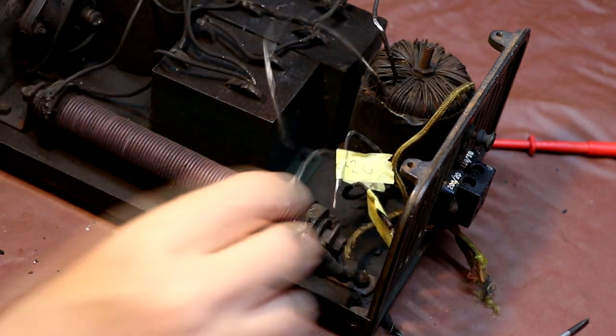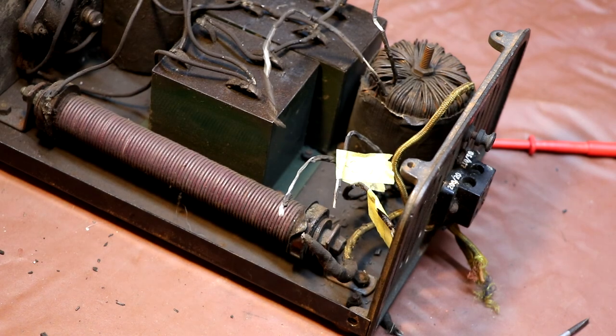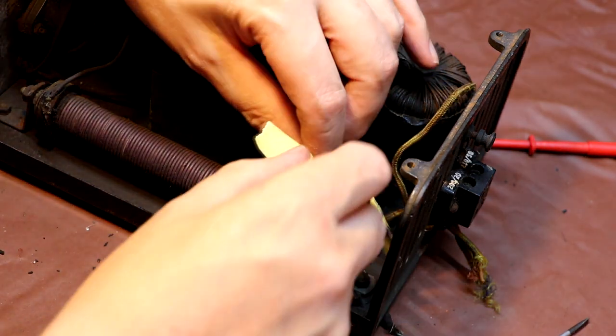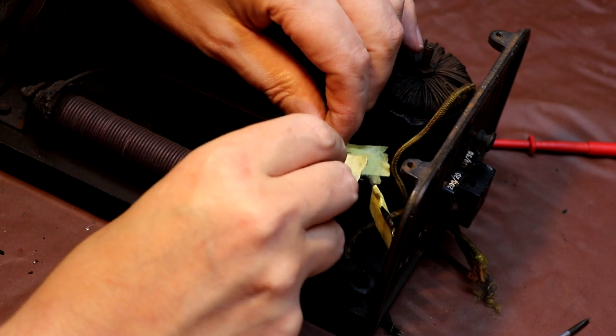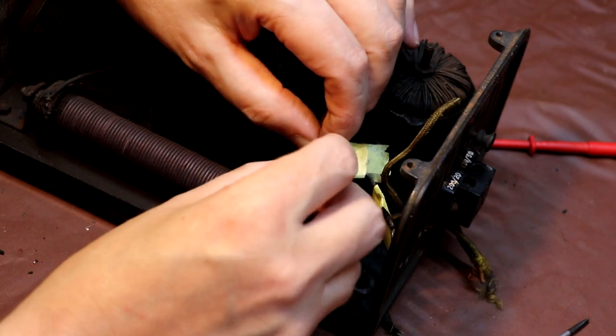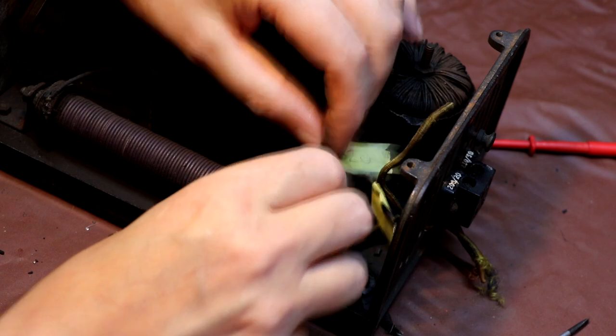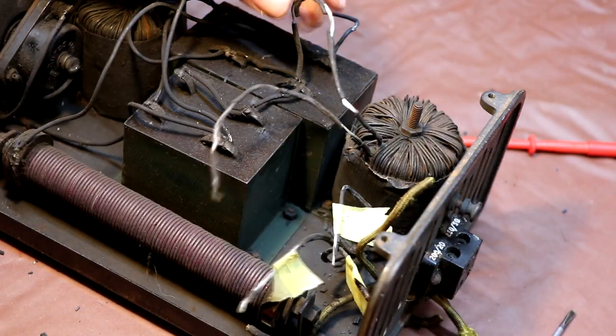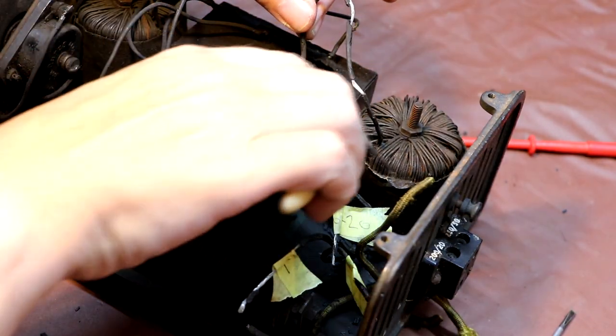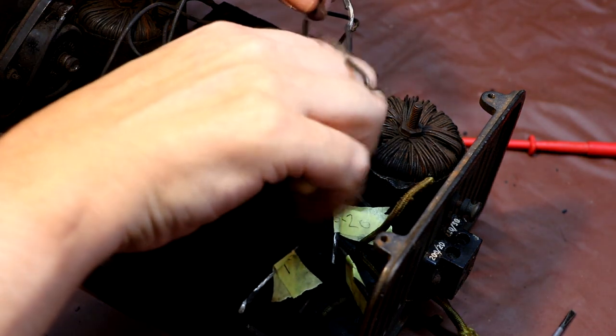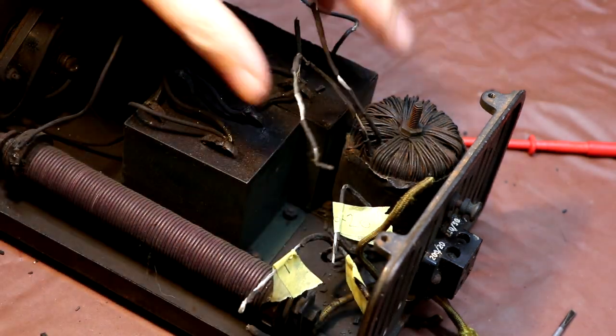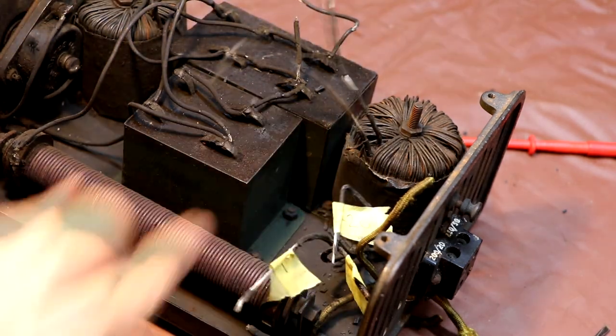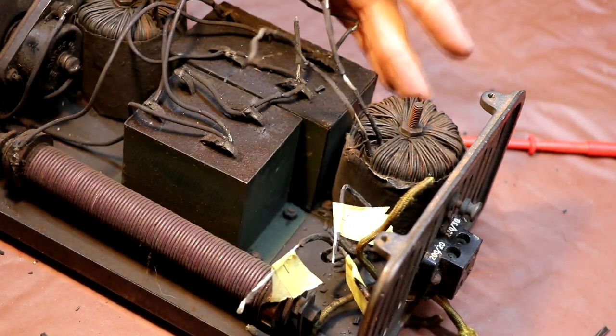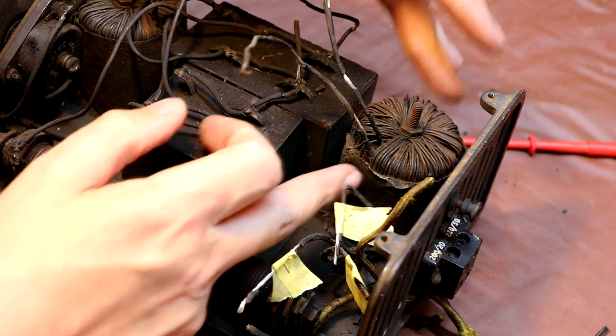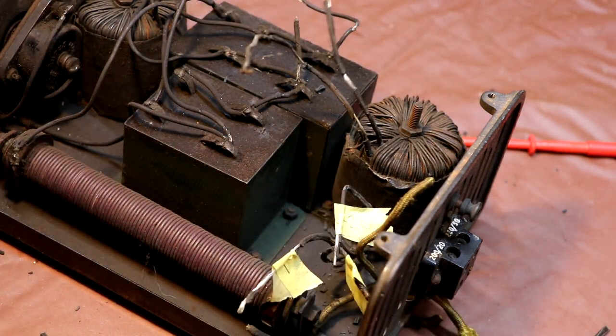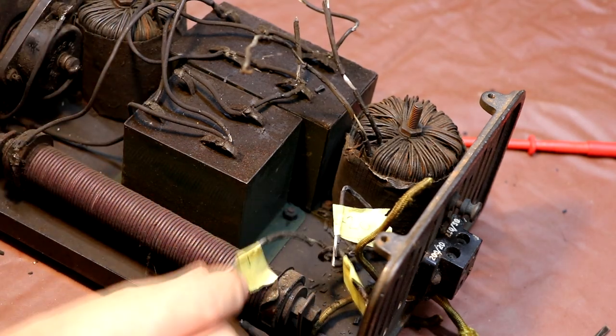And I think I will mark it live, although we know what it is, don't we? I'm going to call it live. It could equally well be neutral. Wouldn't actually make any difference to the operation of it. Now we know that these windings here are secondary, so we're going to give them a cut. And I think to make this transformer a little bit easier to manipulate and look at, we need to take it off the frame, take it out of its enclosure, so we can look at where these windings enter the bottom of it.